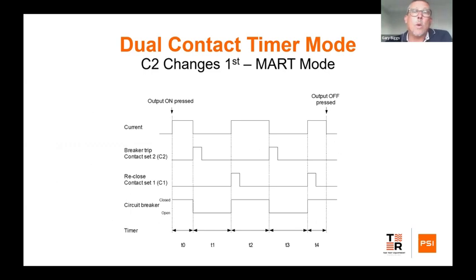So when we download those results, this is what we will see. Here we can see the output was switched on, and we can see that the relay then operates and switches off. And when it switches off, it sees that it's now open. The relay is opened. It'll automatically close that relay again, so we can see that operation time. And when it closes that operation again, the current's still there. The problem is still there, so it closes again, and so on and so forth. And this display, what I quite like about it is, most engineers that are doing protection testing with relays will also do circuit breaker timing, and anyone that's seen a circuit timer display will recognize this as being very, very similar to a circuit breaker timer. The difference is this is for an auto reclosing relay.